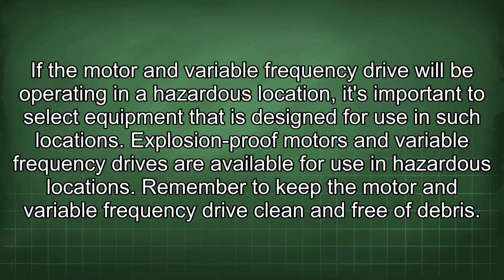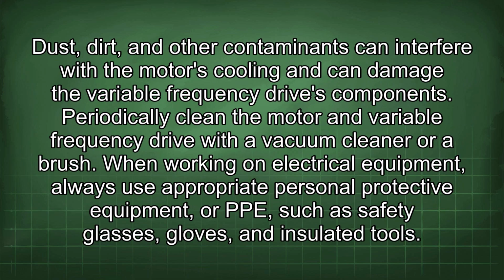Explosion-proof motors and variable frequency drives are available for use in hazardous locations. Remember to keep the motor and variable frequency drive clean and free of debris. Dust, dirt, and other contaminants can interfere with the motor's cooling and can damage the variable frequency drive's components. Periodically clean the motor and variable frequency drive with a vacuum cleaner or a brush.